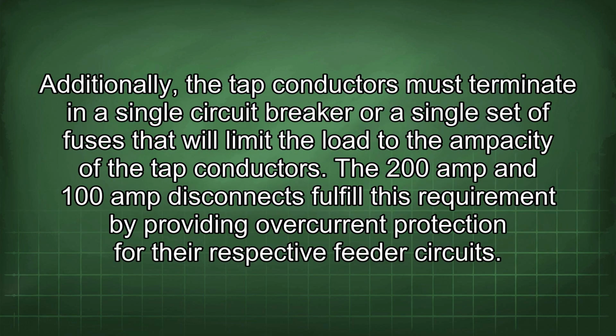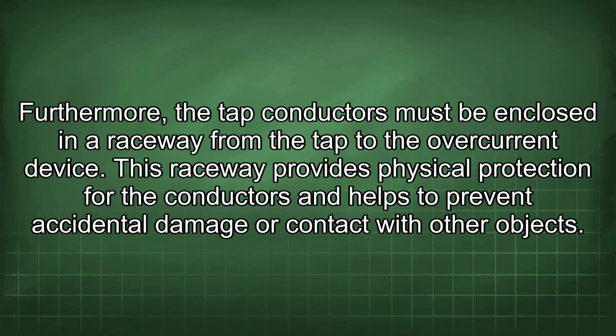Additionally, the tap conductors must terminate in a single circuit breaker or a single set of fuses that will limit the load to the ampacity of the tap conductors. The 200 amp and 100 amp disconnects fulfill this requirement by providing overcurrent protection for their respective feeder circuits. Furthermore, the tap conductors must be enclosed in a raceway from the tap to the overcurrent device. This raceway provides physical protection for the conductors and helps to prevent accidental damage or contact with other objects.